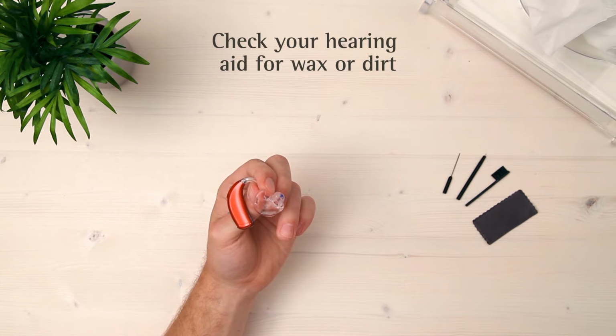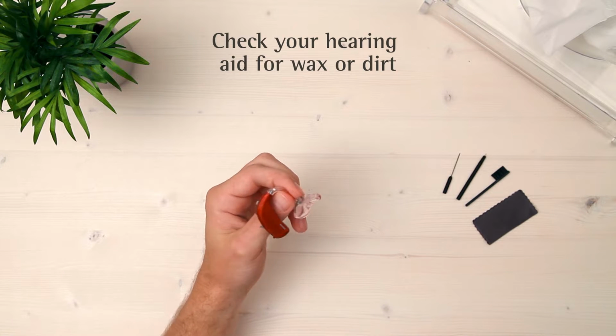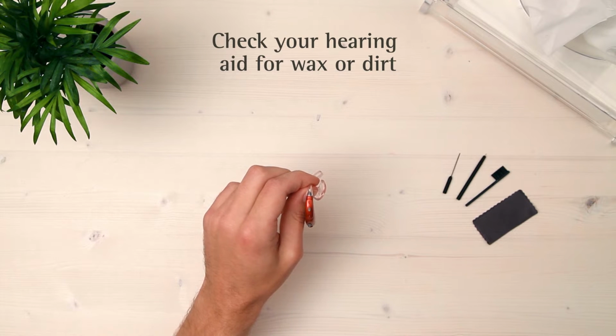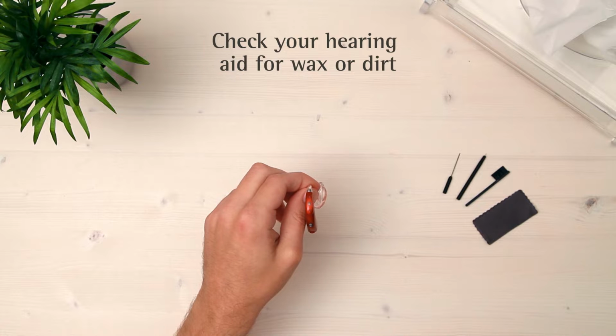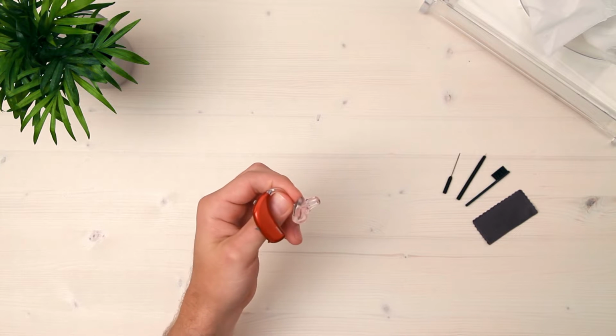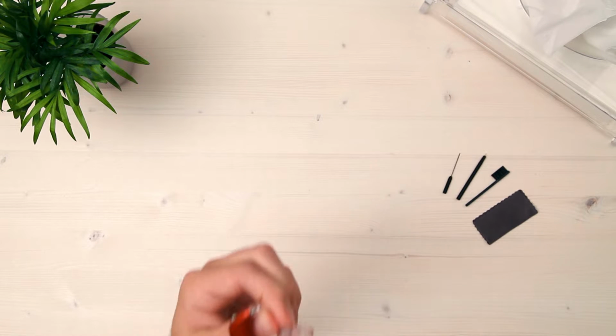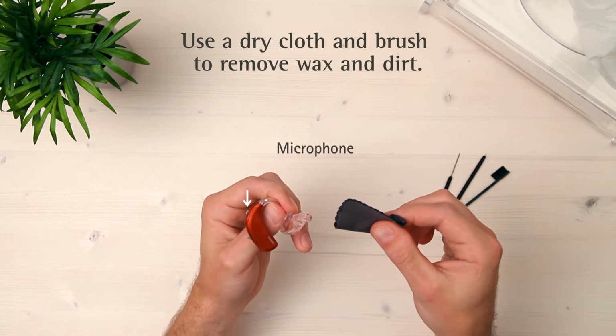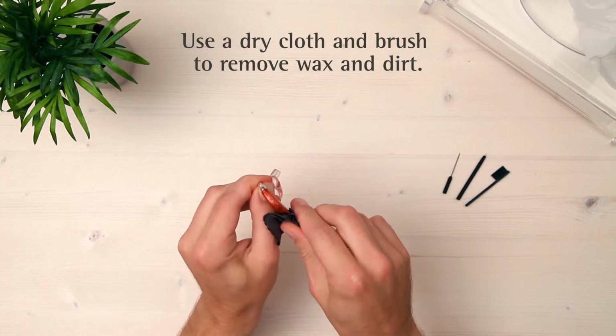First, examine the hearing aid. Check for any wax or dirt. Pay particular attention to the end of the ear mold that fits into your ear and the top side of the hearing aid near the microphones. Use your clean, dry cloth to remove wax and dirt from the hearing aid.